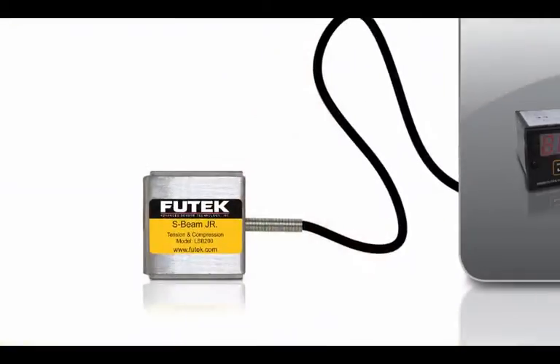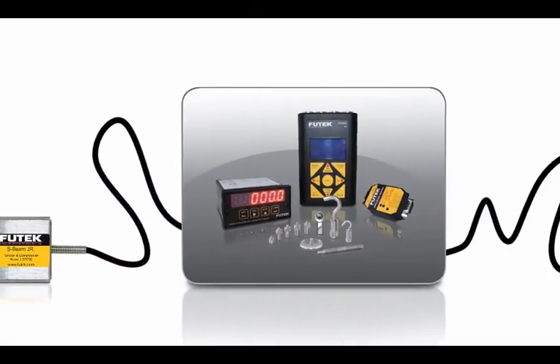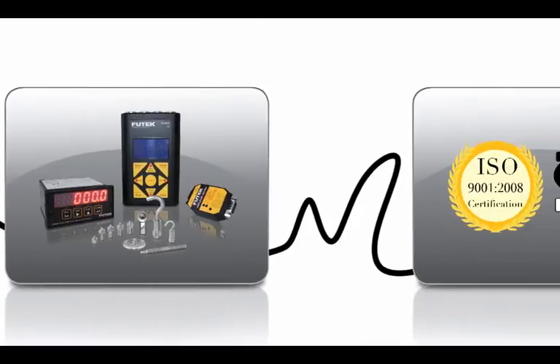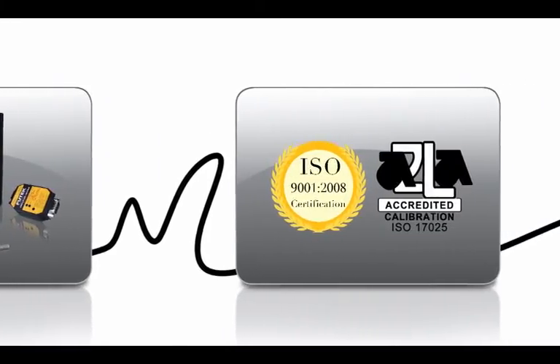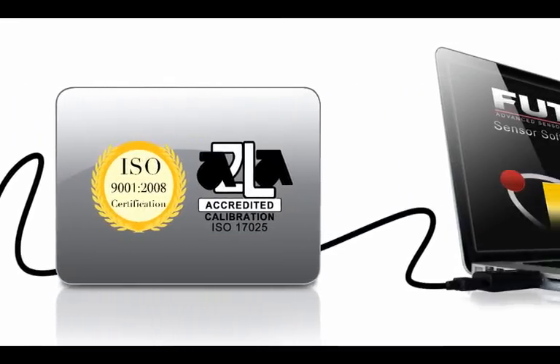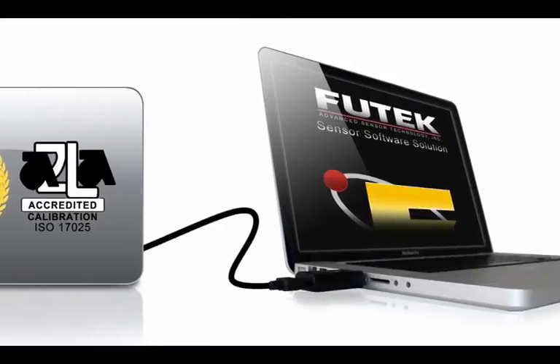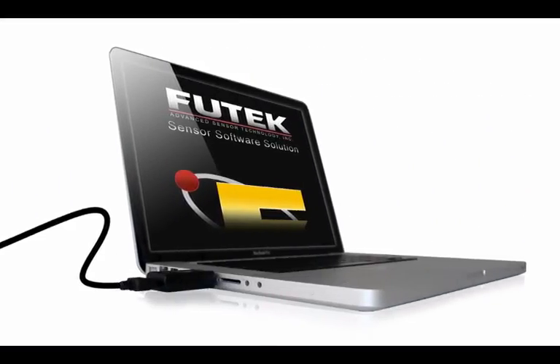Along with these instruments and the LSB 200, we can actually calibrate those here for you too. We have an ISO 17025 A2LA accredited calibration lab that can take the sensor and the electronics and combine them into a system calibration. With the system calibration, the customer gets a predefined, pre-set-up system in the engineering units they require. All they do is receive the product, plug it in, install it in their system, and they're off and running.